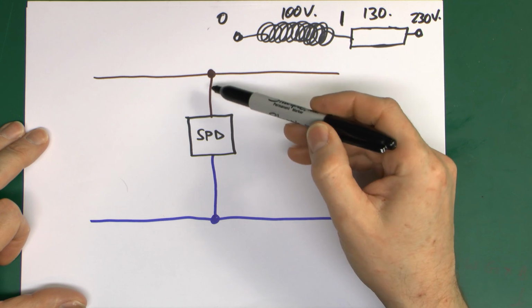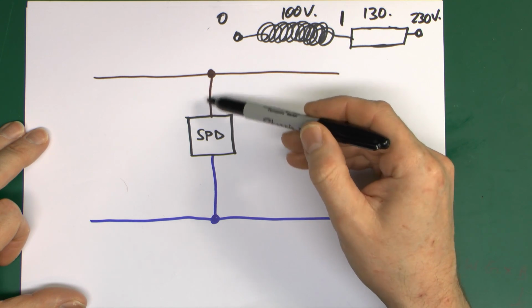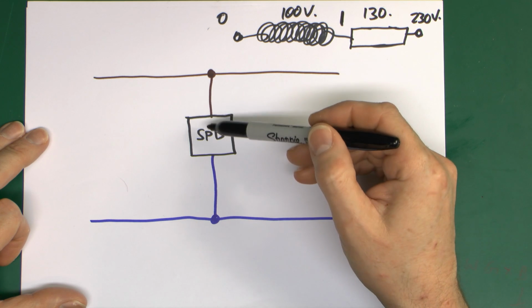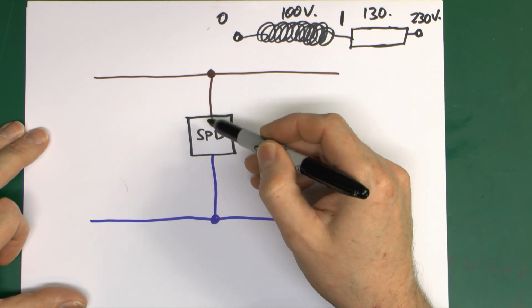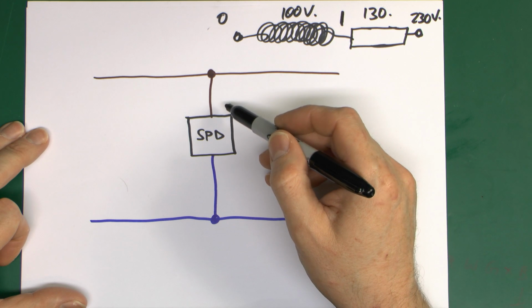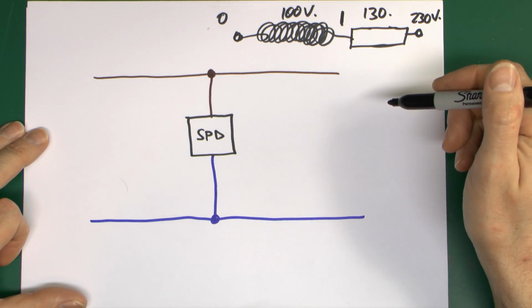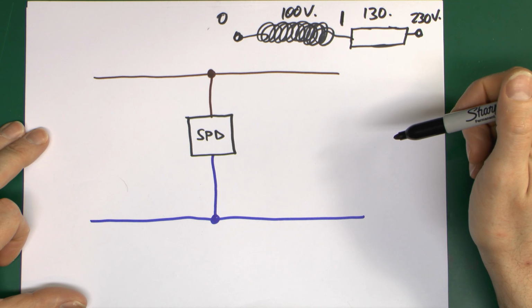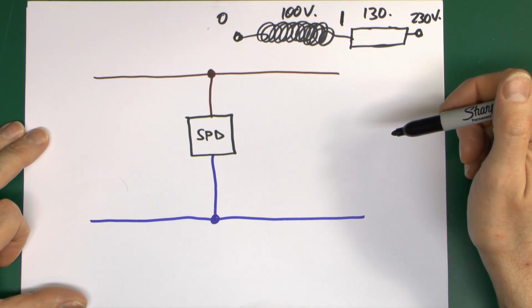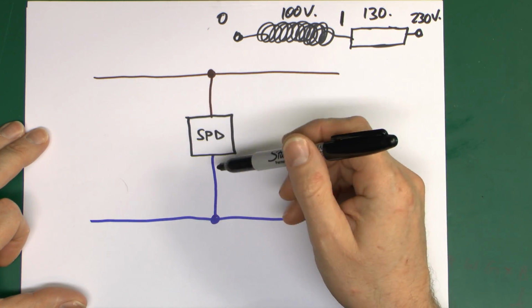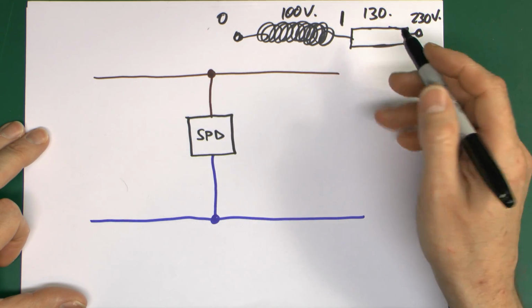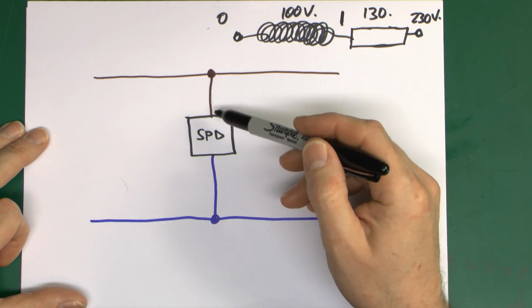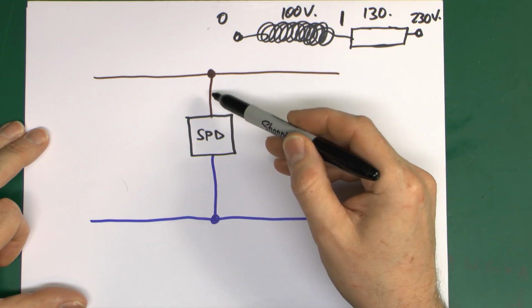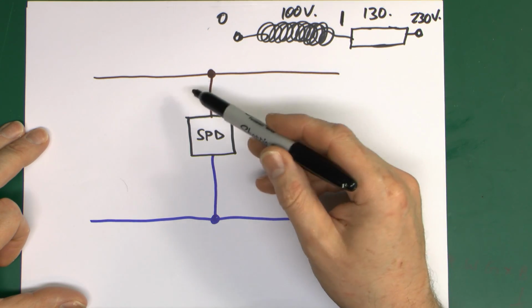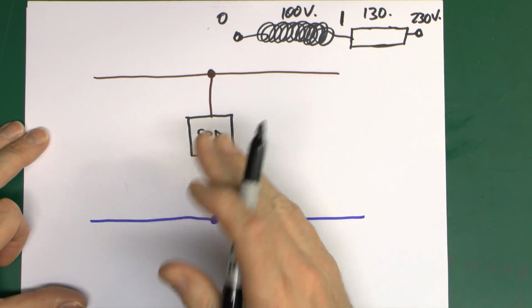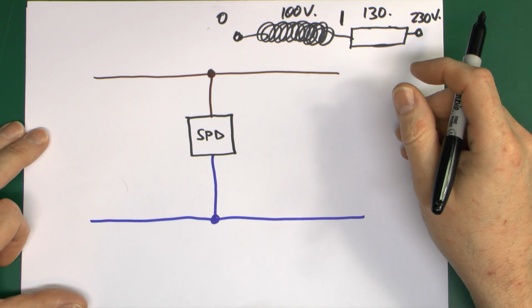Now what might be less obvious is that although this is just a straight piece of wire, it does actually have some inductance as well. And of course the inductance of a straight wire is absolutely minute. It's in the sort of microhenries range, so in normal applications at 50 hertz or whatever, it's not even significant, so tiny that it makes no difference to anything. But of course surges are not 50 hertz electricity coming in here. It's a very short and very sharp and spiky kind of pulse, so even a tiny little bit of inductance here can be significant when you're talking about very high rise time or intense pulses.